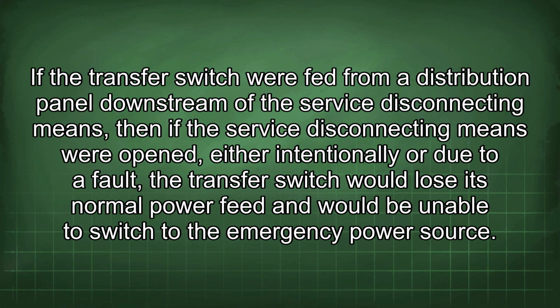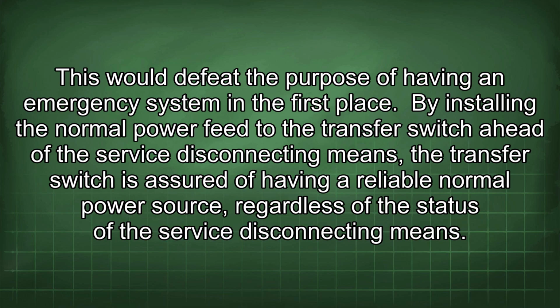If the transfer switch were fed from a distribution panel downstream of the service disconnecting means, then if the service disconnecting means were opened, either intentionally or due to a fault, the transfer switch would lose its normal power feed and would be unable to switch to the emergency power source. This would defeat the purpose of having an emergency system in the first place.